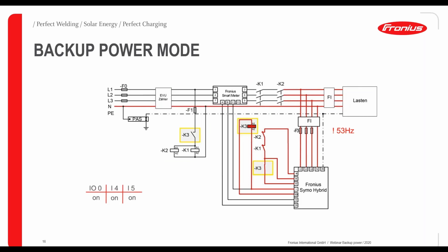In the backup power mode, we first detect there's no voltage. K1 and K2 will immediately switch off. So there's no supply here. On L1 there's no power. The two contactors here are switching off. So they insulate the AC side from the loads and the hybrid inverter.